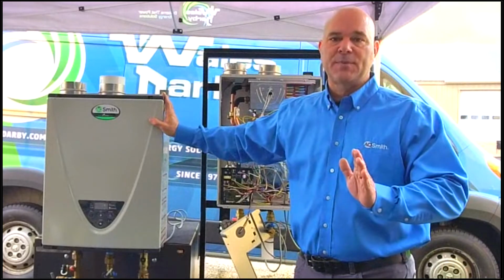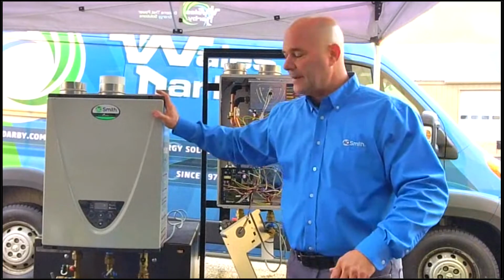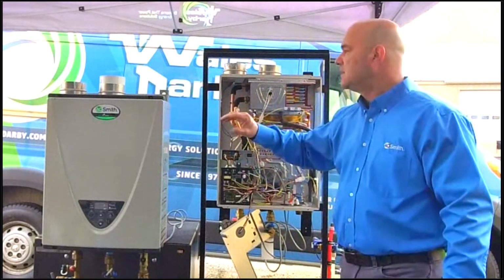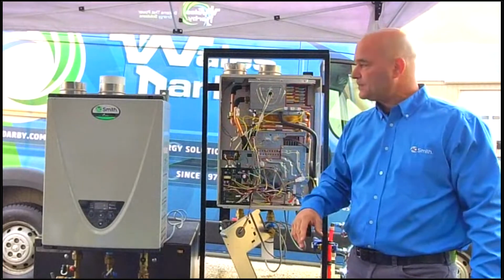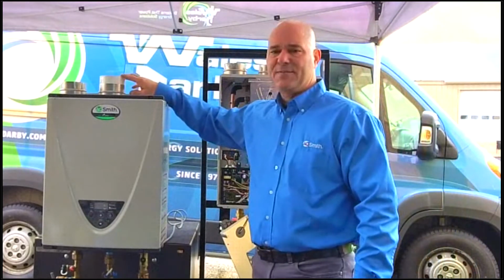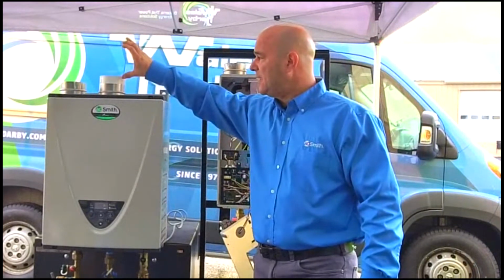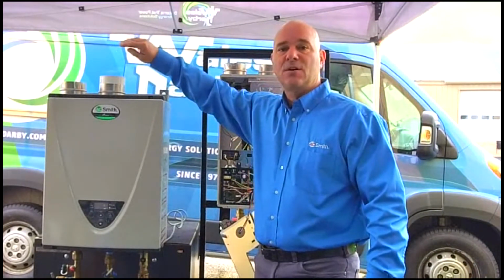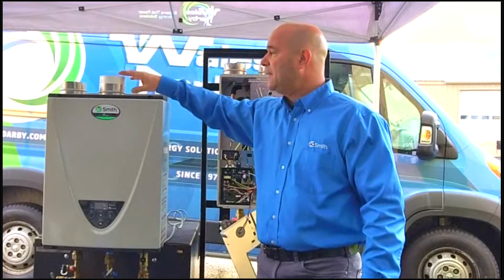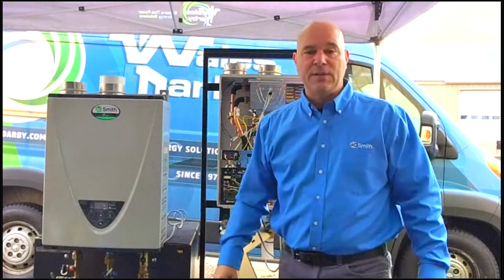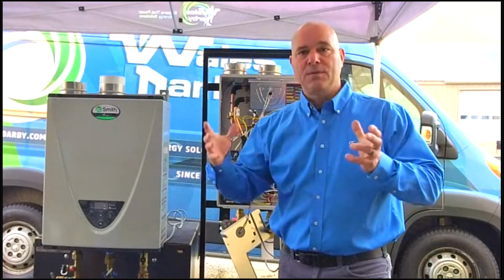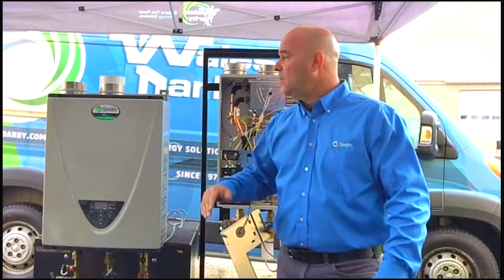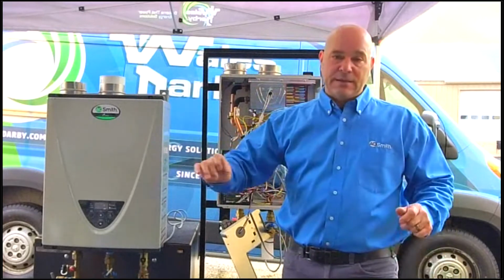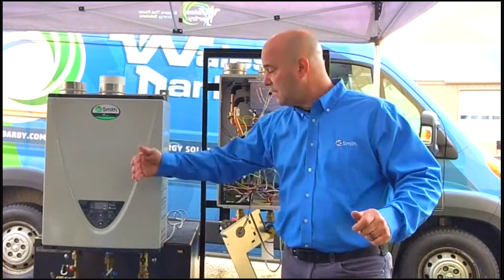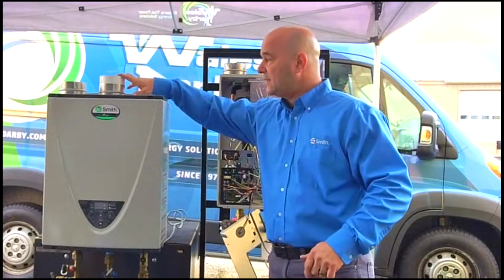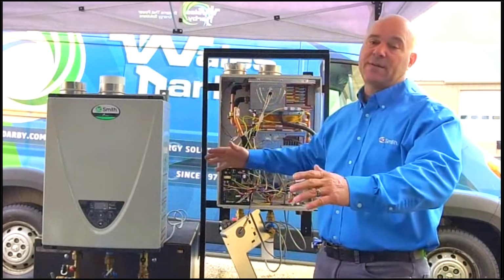So it depends on what type of job you're doing. You've got a hotel, whatever it may be. You have the options of going tankless. So up to 20. From a venting standpoint, we now have the ability to common vent. All right, there's an adapter you get on here with a check in there so that you can't exhaust into any of the heaters within the space, and you have the ability to exhaust multiple heaters through one common hole, let's say a 6-inch termination. So we can do multiples from a connection standpoint to have them work with each other. We can do it from a venting standpoint, and we also have what's called a rack system.